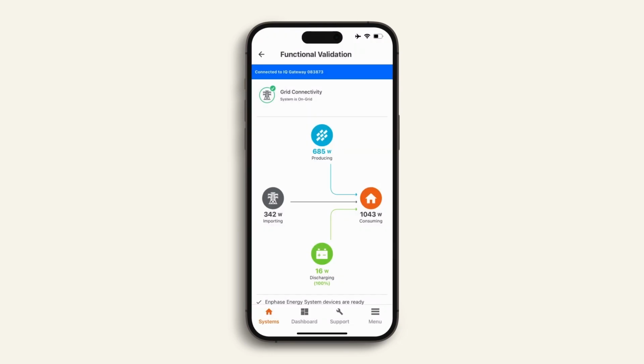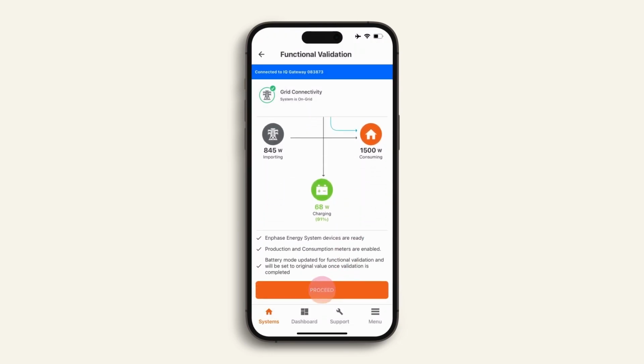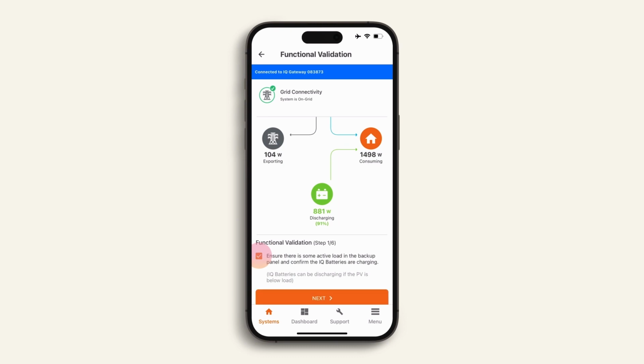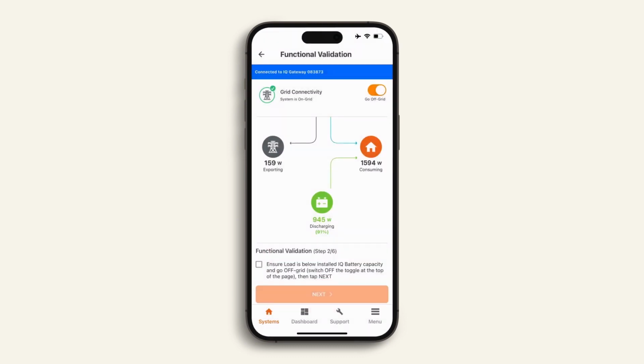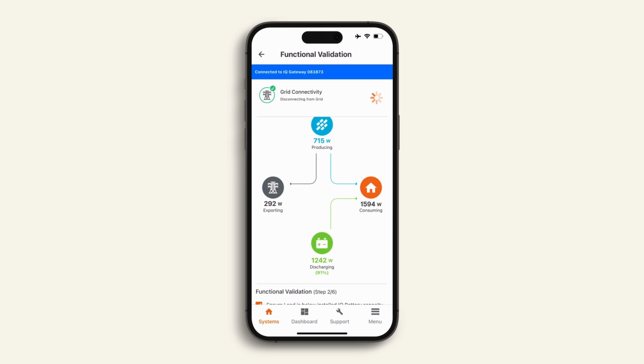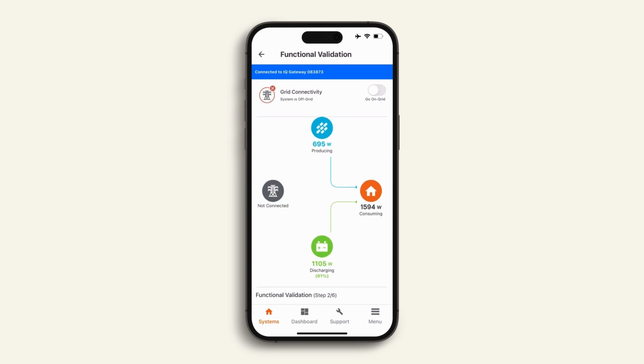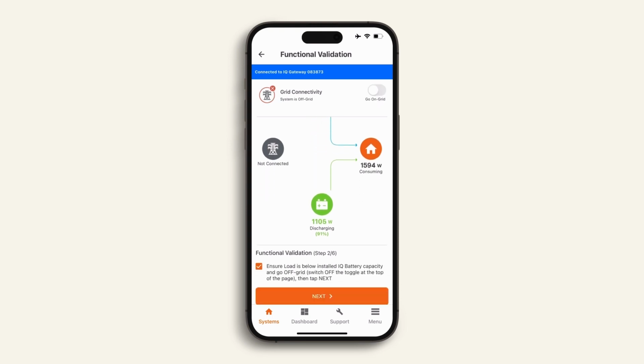This is where the energy system will test that your installation can operate and transition between on and off-grid modes. For each of these 6 steps, follow the on-screen instructions and toggle the switch to the top right of the screen when instructed. For step 2, you will check that the load is less than the capacity of the IQ batteries. Once you've confirmed this, toggle the switch to off-grid. You are now running in off-grid mode. The loads are running directly off the Enphase energy system. Turn on more loads to ensure the system is supporting the load and continue to work in off-grid mode.